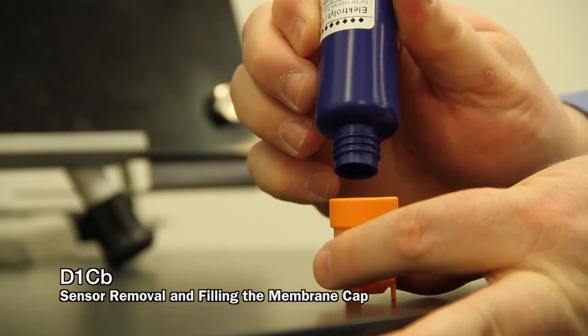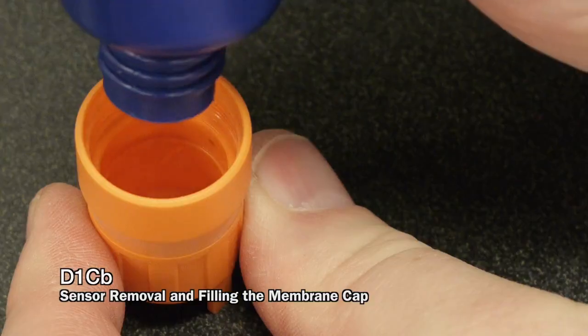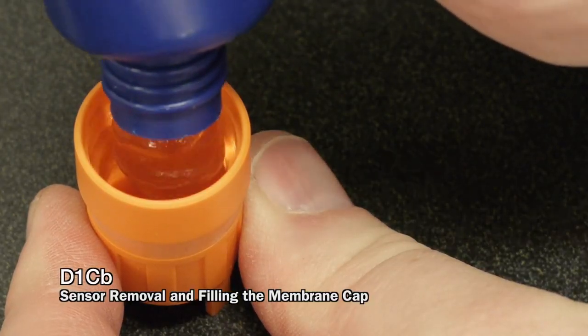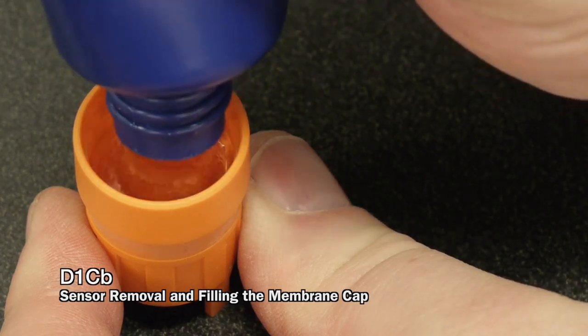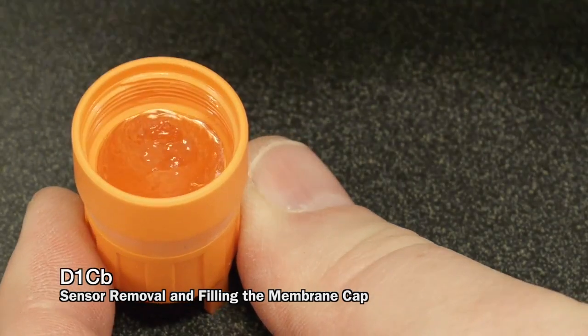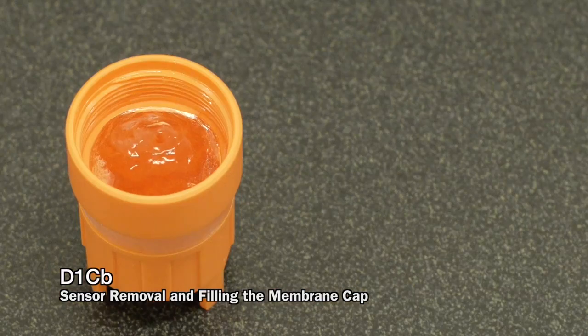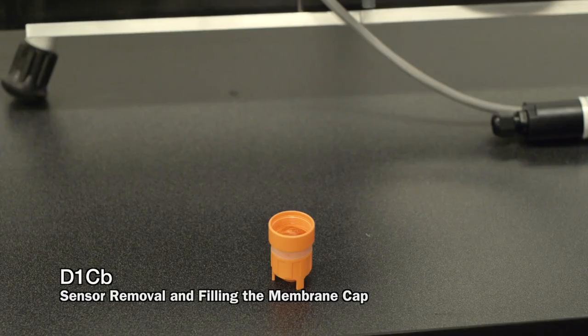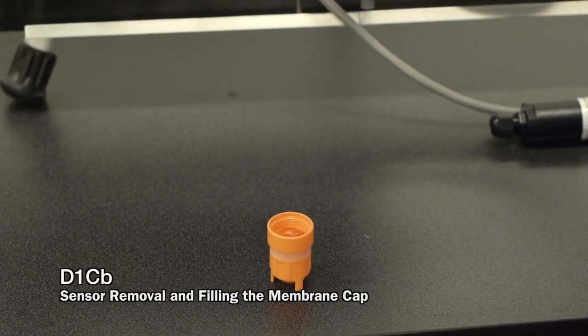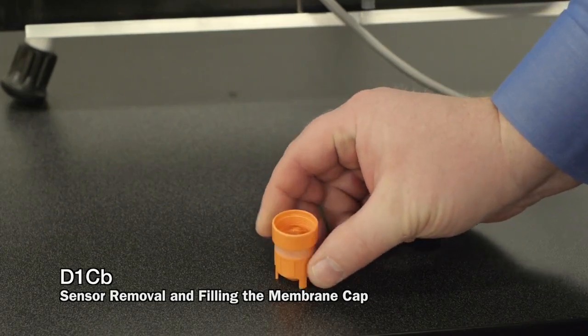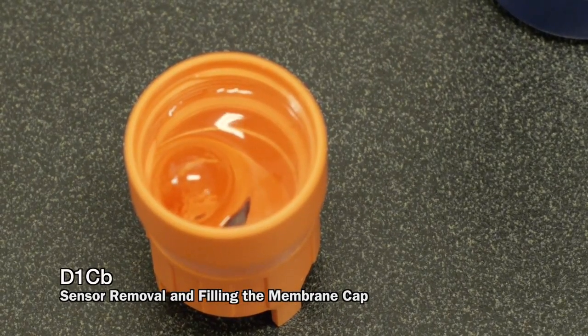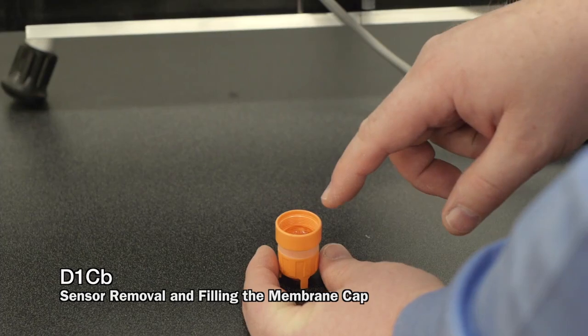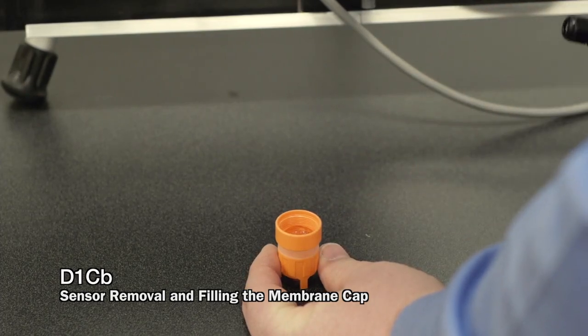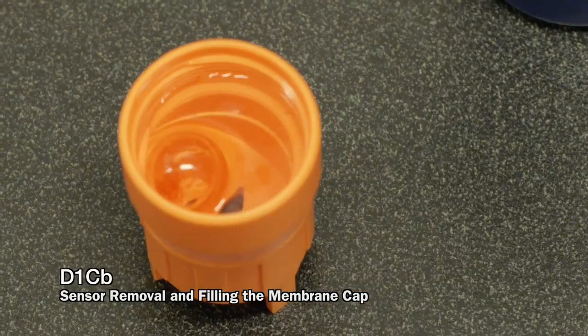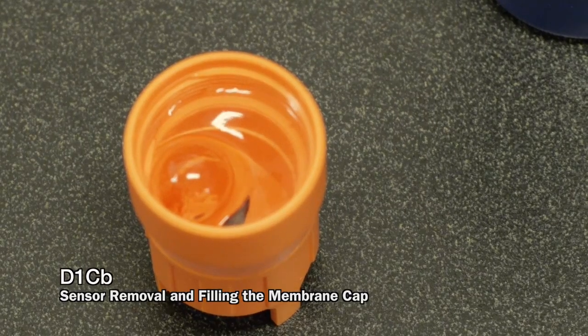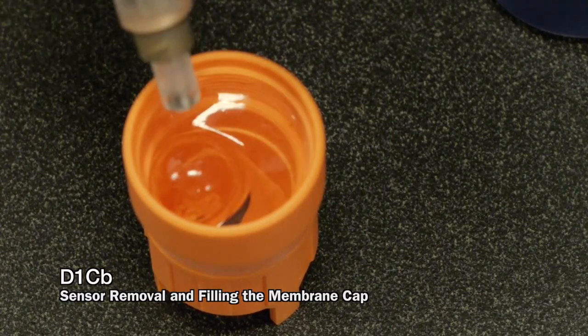We're going to fill that cap with electrolyte. Here you can see how much thicker the electrolyte is. We want to fill it, again, so there's no air bubbles. If there is an air bubble, that air bubble will migrate towards the top in time. We'll let that come to the top. Never put a screwdriver or any other instrument into the electrolyte. If you want to try to help remove the air bubble, use the sensor tip itself.